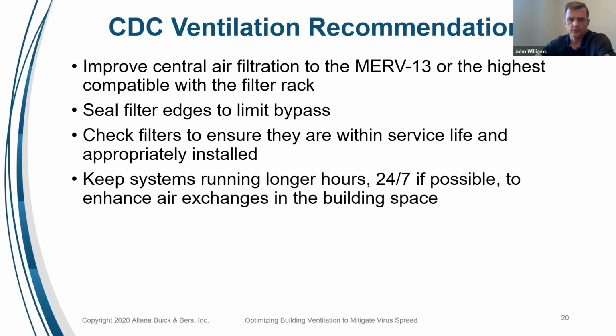Lastly, the last point on the CDC recommendations is run the systems. Most systems nowadays have programmable thermostats, smart thermostats, and we go to these unoccupied settings or setbacks. But now, with the increased sensitivity to ventilation, we want to run these things as much as we can, as Kareem mentioned before, for air changes, and to turn over the air in the building and to keep the air movement going in the building. Right now is not the time to be concerned about your energy conservation as much as it is about ventilating your building.